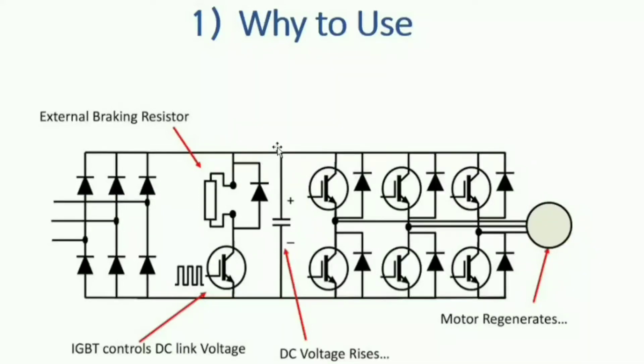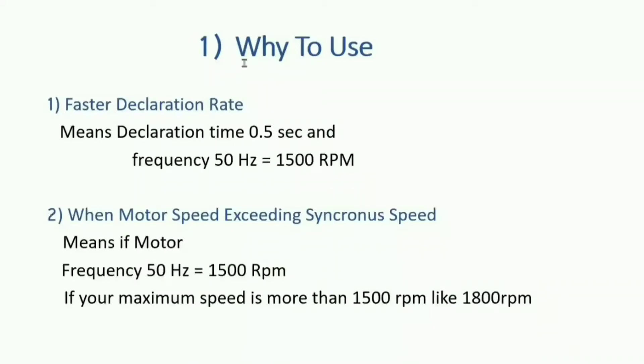If we don't control the overvoltage, it can damage the rectifier, IGBT, or card. The circuit senses the over-voltage DC level and switches on the braking IGBT. The voltage then goes through the resistor to the negative rail, and the excess voltage is dissipated as heat. There are two types of applications where we use the braking resistor.